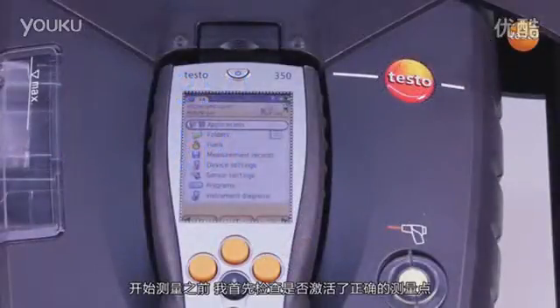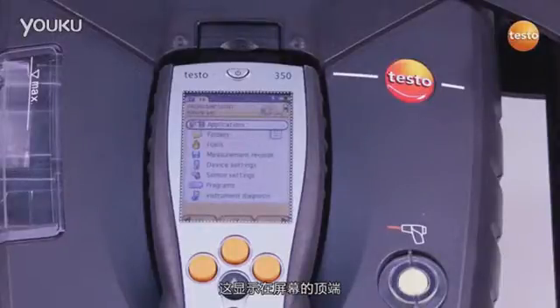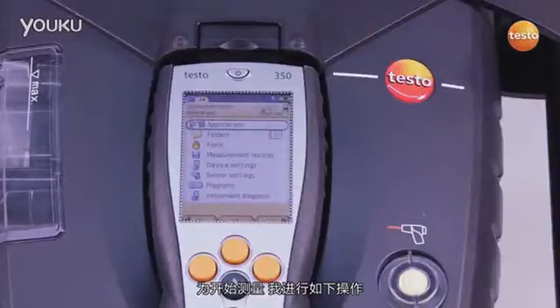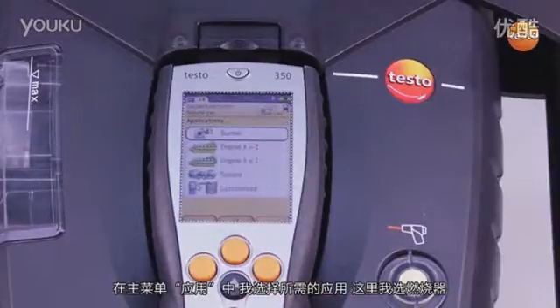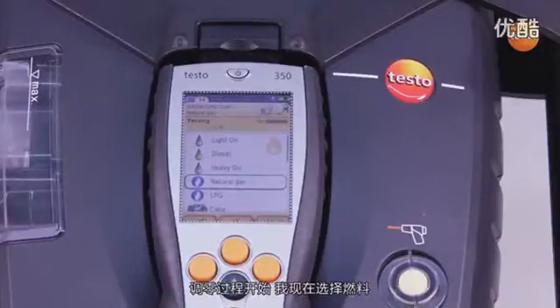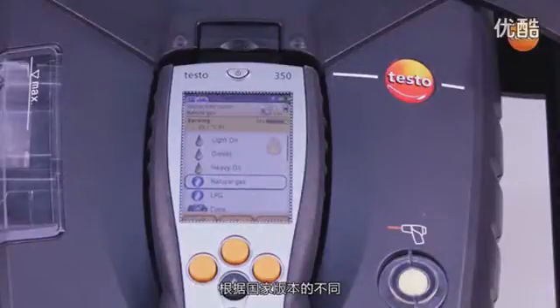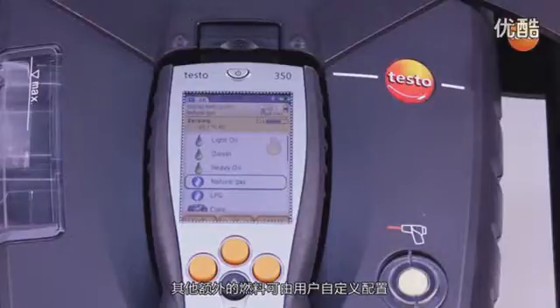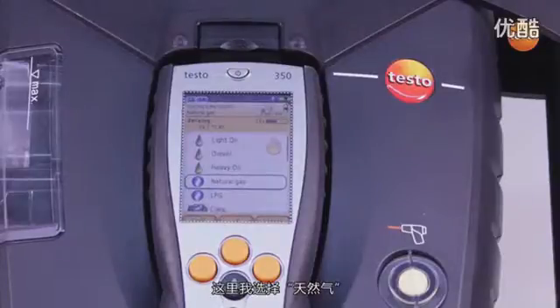Before I start the measurement, I check whether the correct measurement location is activated. This is shown at the top of the display. To start the measurement, I proceed as follows. In the main menu Applications, I select the desired application, in this case a burner. The zeroing phase then begins in the background. I now select the fuel. Depending on the country version, a list of fuels is stored, and other additional fuels can be configured customer specifically. In this case, I select the fuel natural gas.